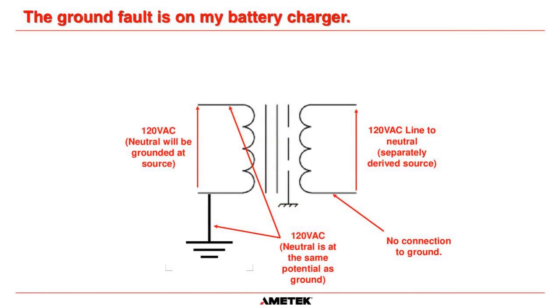So what I mean by this is, let's take a 120 volt AC input into a transformer to explain what's going on. The neutral for any system will be grounded at the source, and it should only be grounded at one point. So the neutral is intentionally tied to ground on the primary of this transformer. But you can see here that this is an isolation transformer. There is absolutely no connection between the primary and the secondary. No electrical connection whatsoever. So, although we do have 120 volts AC line to neutral on the secondary of this transformer, it is now a separately derived source, and there is no connection to ground unless somebody has actually done that.